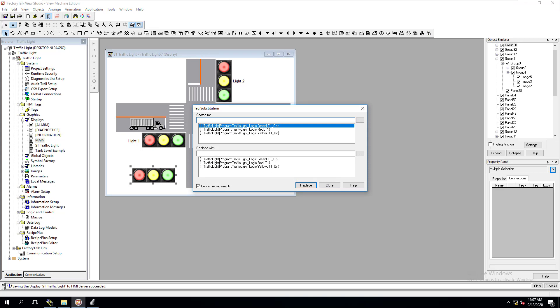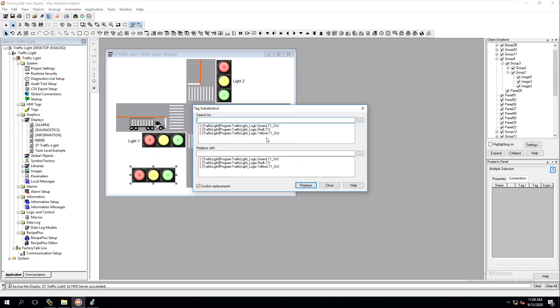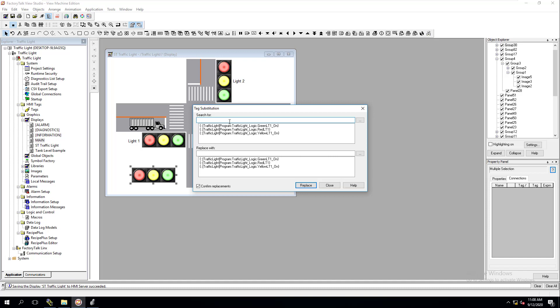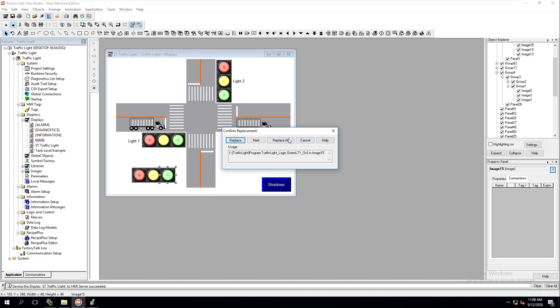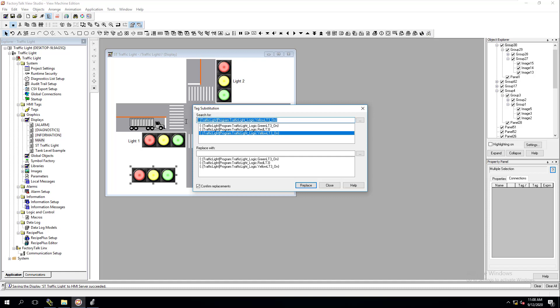If this was light three, what we could do is say L2 and then L3 and then replace that. So then this would be light three — we don't have any tags for light three, but you can easily see. Let me come in here and do LT1 because I did LT2. Make sure that you're replacing the right thing — I did LT2 and there's no LT2, it couldn't find anything. So I did LT1, we'll replace this and make sure it says tag substitution performed six tags. So tag substitution performed six tags — now they're all the same. Make sure you double check.